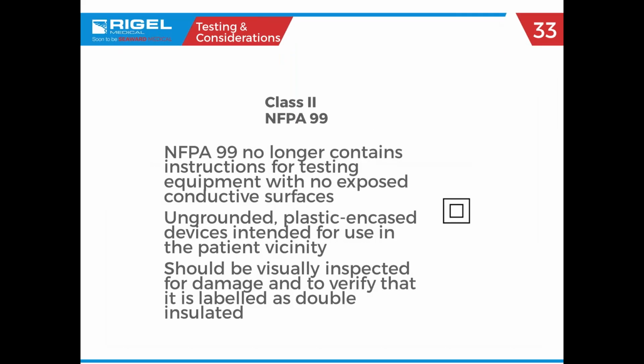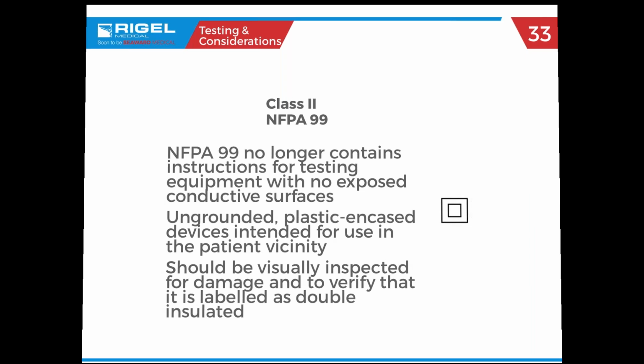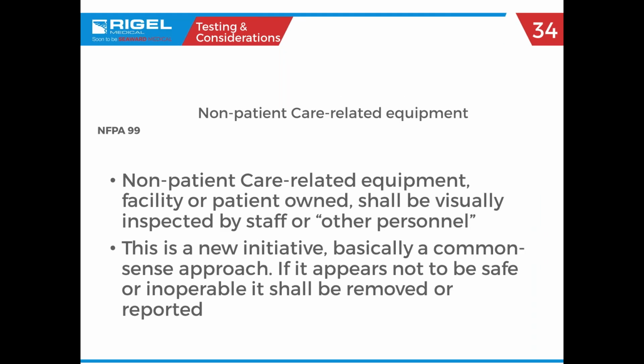Okay, so here's the change that happened in the 2015 revision. They said that no testing was needed for equipment with no exposed conductive surfaces, and ungrounded plastic encased devices intended for use in the patient vicinity should only be visually inspected for damage and to verify that it is labeled as double insulated. So no more testing of class 2 devices, basically.